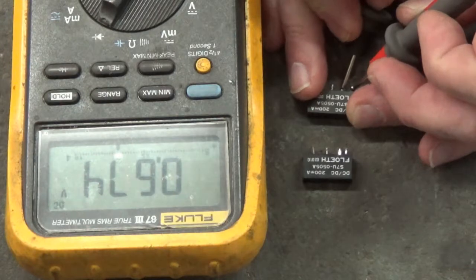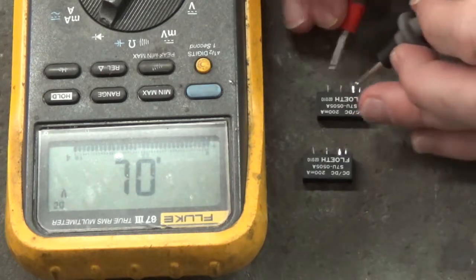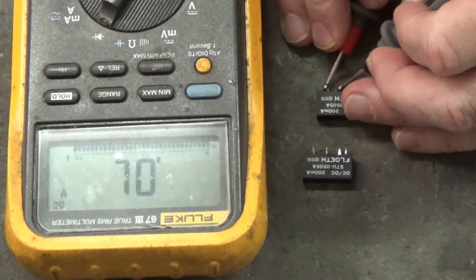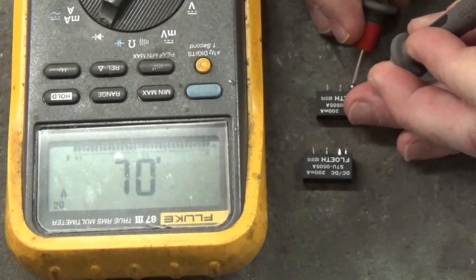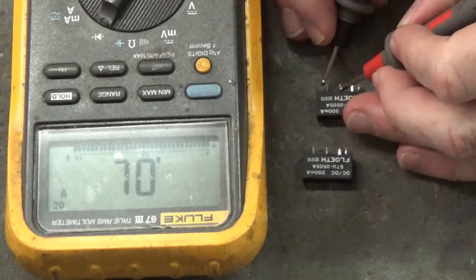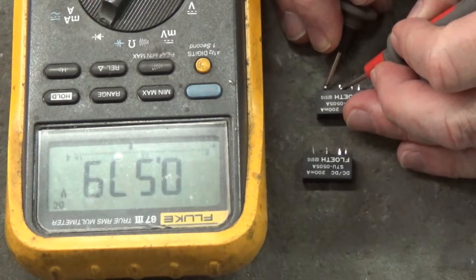Let's go to the output side and see what we've got there. I got the black lead on four and the red lead on six, and we've got an open circuit right there. Let me reverse the leads on both these. I've got an open circuit right there. Now I'll put the red lead on four and the black lead on six. Look at that, I got a diode drop right there on the output side, point five seven nine.